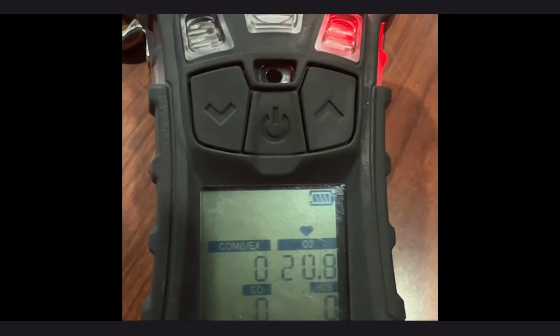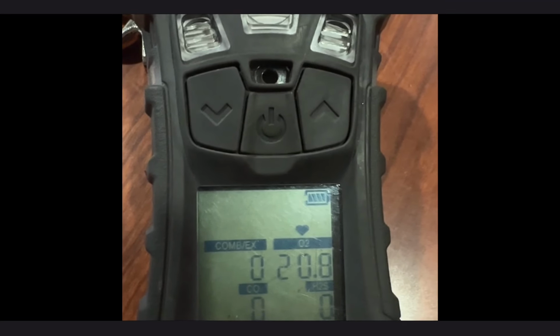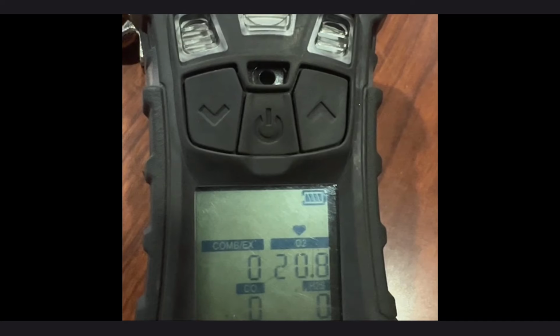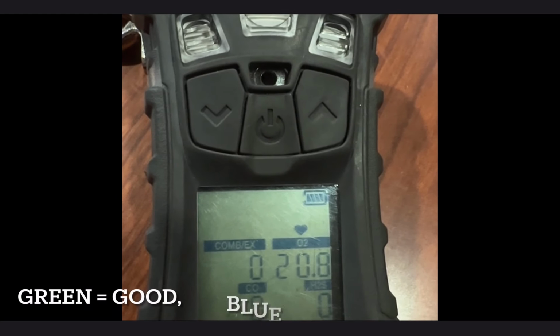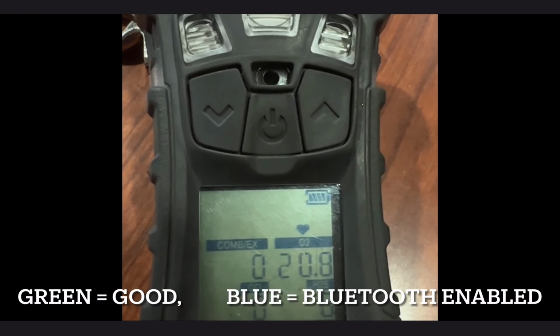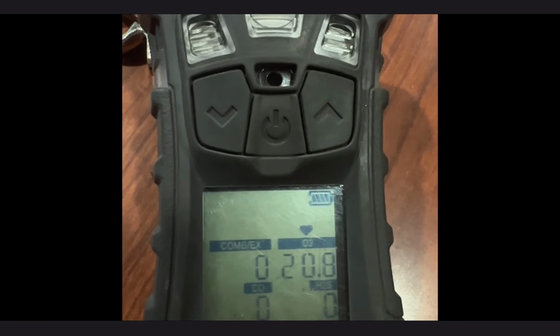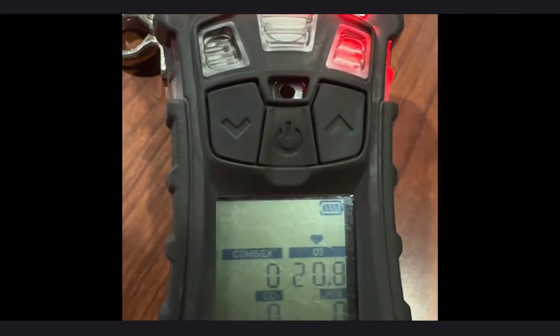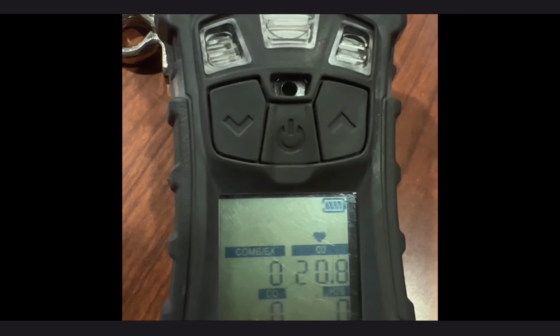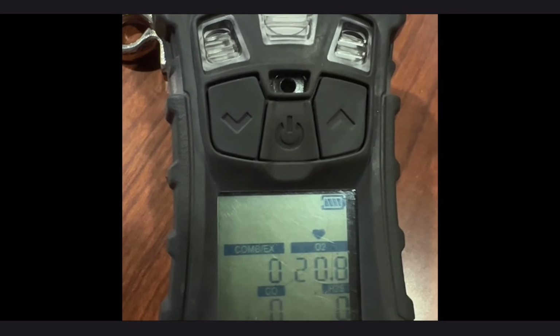So give me an email. And you also have the green, which just means it's good. Sometimes you'll see monitors light up blue. They can be dropped. We don't do it, but people drop them in hot zones to monitor remotely. So that's just the Bluetooth setting reading in the background. If it is flashing blue, it doesn't matter. It doesn't affect our readings or monitoring.